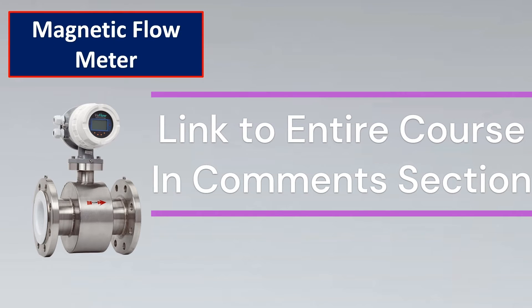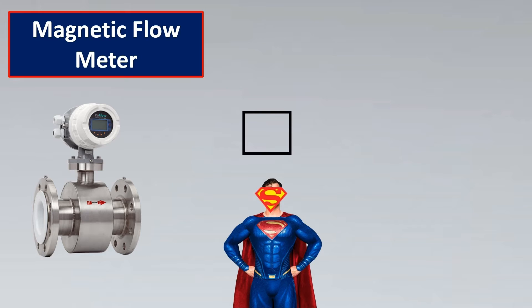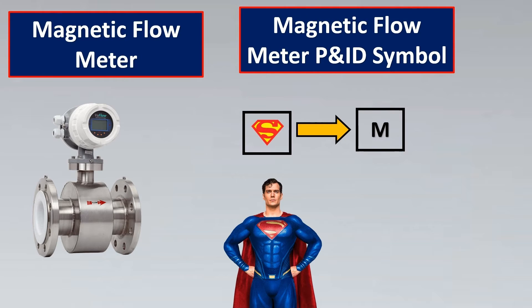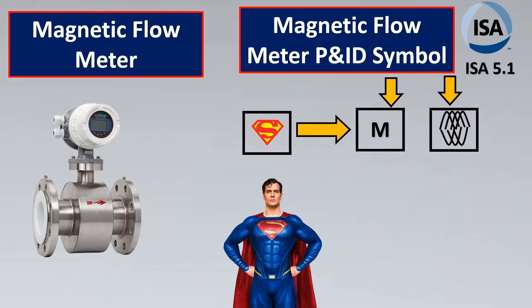Magnetic flow meters are very similar to Superman — just as the 'S' is the most important thing in Superman, the 'M' is the key element for a magnetic flow meter. The P&ID symbol is sometimes shown as an 'M' inside a box, standing for magnetic. ISA 5.1 also provides another symbol based on the construction of magnetic windings, where the elements inside the box represent the magnetic coils.